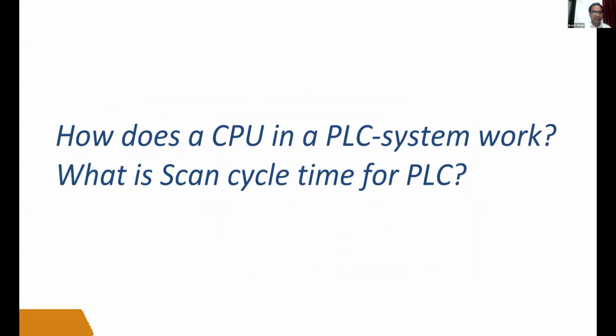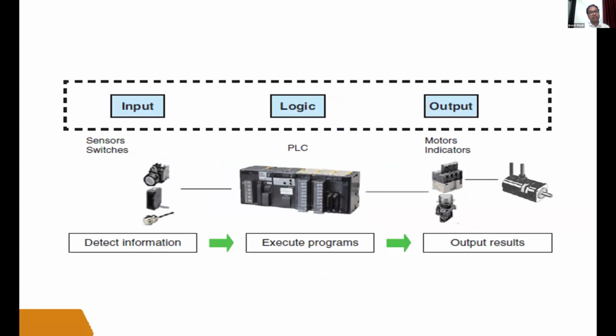Now see here, how exactly the CPU of the system will work. First of all, it will detect the information, which inputs you have connected. And according to the program made by you or made by an engineer, the processor will execute the program, and according to the program, you will get the output here. So this is a very simple working style of the PLC. Even any electrician who has quite a knowledge about the PLC and program can easily work on the PLC system. Why am I telling this? Because we want to implement this system for the agriculture land. In that way, I am telling we can use the PLC.